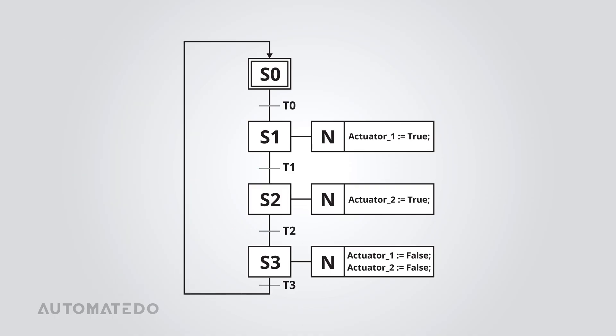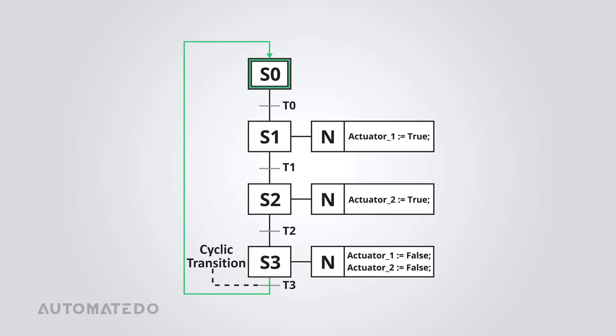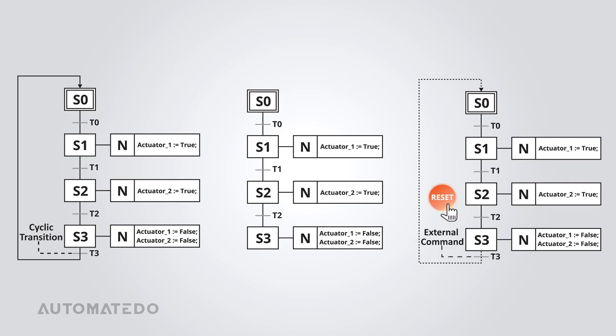SFC programs always start at the initial step, right at the top of the chart. When the program is running, it stays in that step and continuously scans the logic until the transition condition becomes true. The moment that happens, it moves on to the next step and then the next, following the sequence until it reaches the final step. What happens after that depends on the program setup. If you've set up a cyclic transition, the process loops right back to the beginning and runs continuously. If it's a one-time operation, it just stops at the last step. But in some cases, the program might wait for an external command to reset and start over.